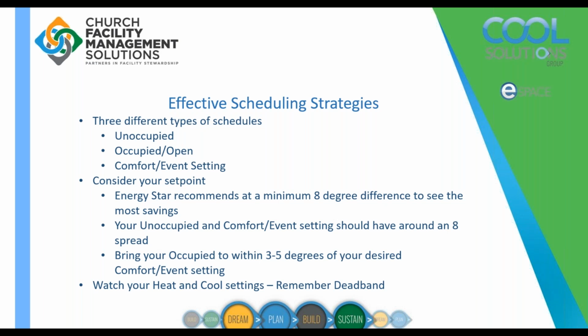So, and then watch your heating and cooling settings. Remember that deadband we talked about earlier. If you put it too close, you're not keeping it rigid on that set point. You're just hurting your equipment. It's designed to have, and if you look at the graph, you'll see your set point, and you should see a sine wave. And that's normal, and that's what you're looking for, and that's what it's designed for.